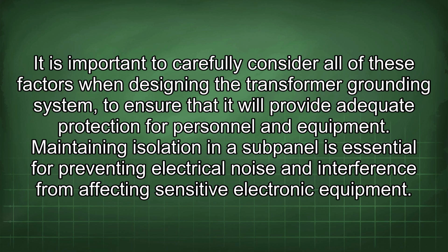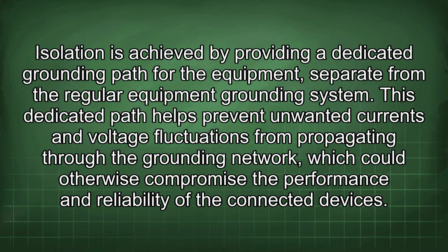Maintaining isolation in a subpanel is essential for preventing electrical noise and interference from affecting sensitive electronic equipment. Isolation is achieved by providing a dedicated grounding path for the equipment, separate from the regular equipment grounding system. This dedicated path helps prevent unwanted currents and voltage fluctuations from propagating through the grounding network, which could otherwise compromise the performance and reliability of the connected devices.